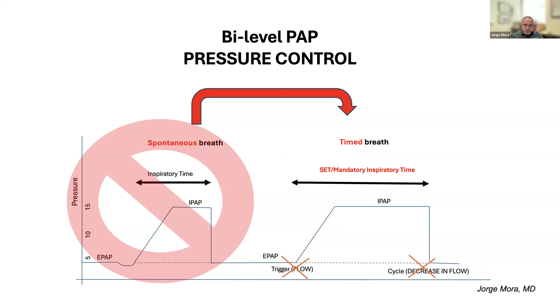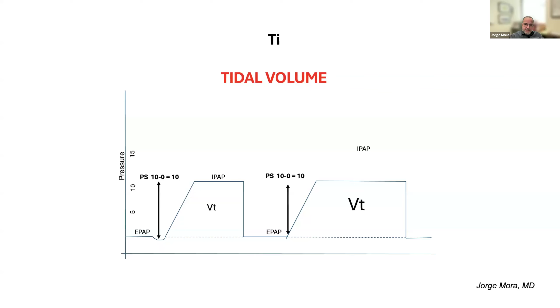This is essentially what I just explained. There is no trigger. The cycle is not depending on effort or any other variable. This we have inherently mentioned: TI will define tidal volume. The longer you exert that pressure support, the larger the area under the curve, the larger the tidal volume. So for the same difference and same mechanics, longer TI, larger tidal volume.